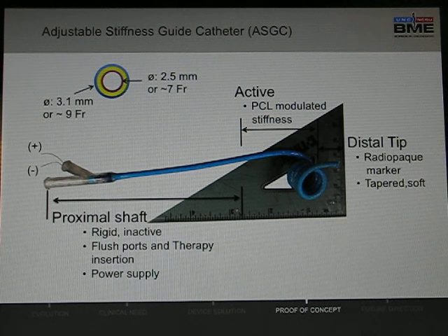So if we look at the cross-section of the active segment, we see we have an internal luminal diameter of approximately 7 French and an outer diameter of approximately 9 French. In red, we have the heating element, and above that, PCL in yellow is deposited. And the PCL is sandwiched between multiple layers of polymers.